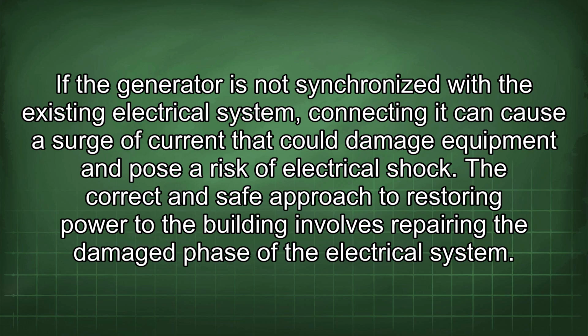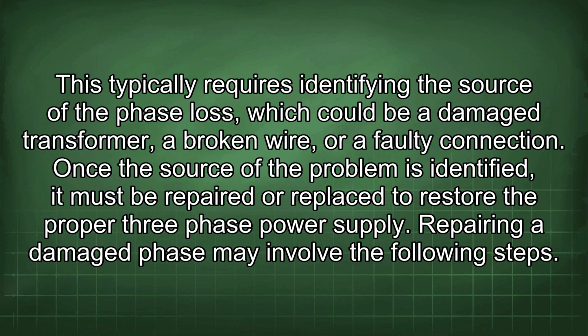The correct and safe approach to restoring power to the building involves repairing the damaged phase of the electrical system. This typically requires identifying the source of the phase loss, which could be a damaged transformer, a broken wire, or a faulty connection. Once the source of the problem is identified, it must be repaired or replaced to restore the proper three-phase power supply. Repairing a damaged phase may involve the following steps.